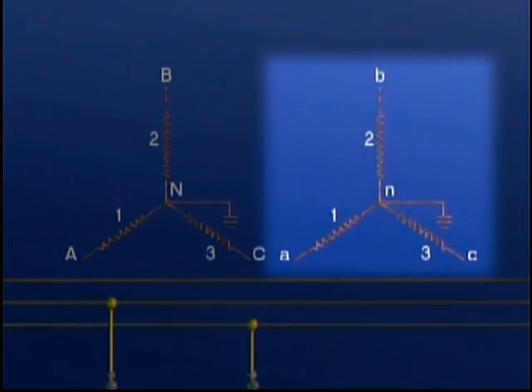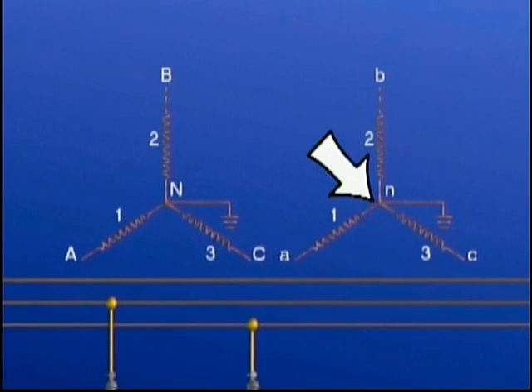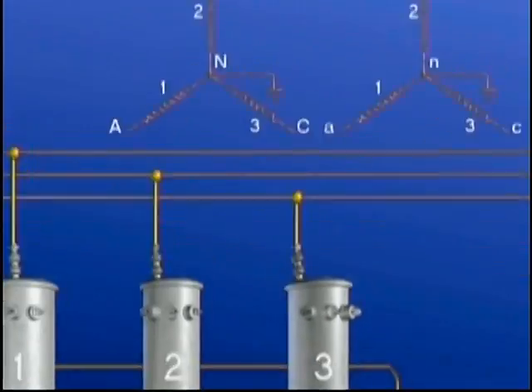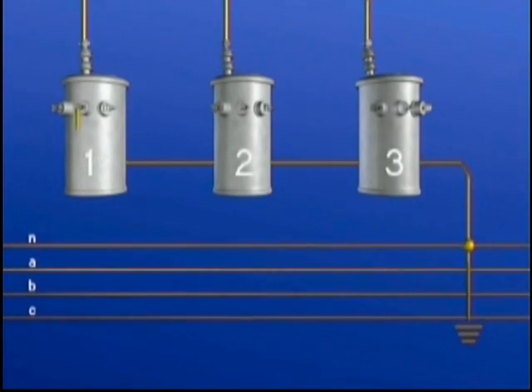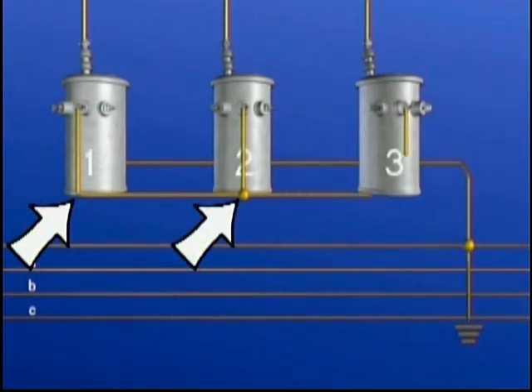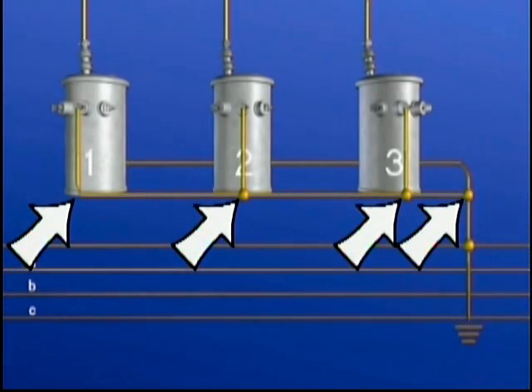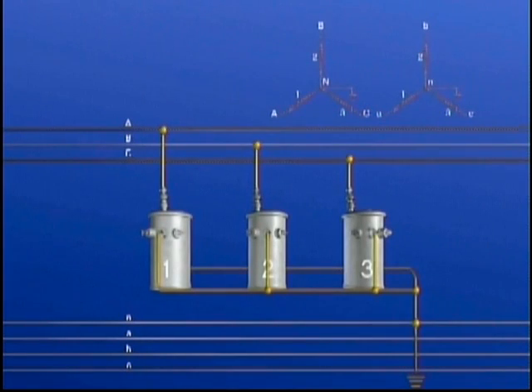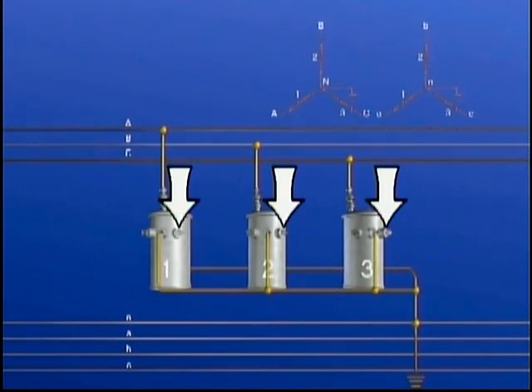As you'll recall, in a Y connection, one end of each winding is connected together at the system neutral. The connection is known as a Y tie. On the secondary side of this bank, we'll use jumpers to connect these ends of the secondary windings attached to the X2 bushings together. We'll then connect this Y tie to the grounded system neutral. With this done, we'll now need to connect the X1 bushing of each unit to the appropriate secondary distribution line.